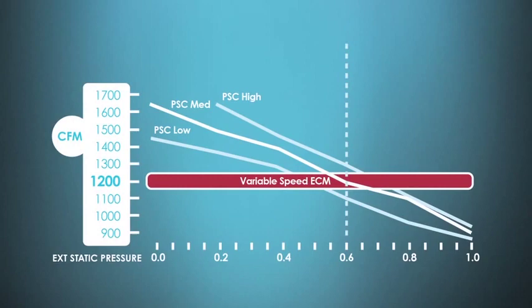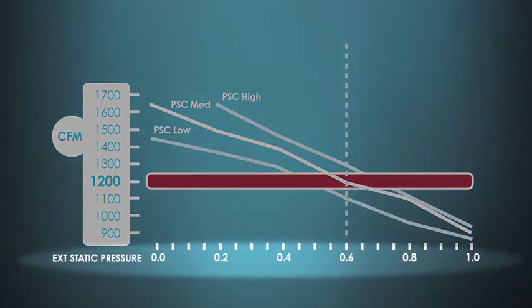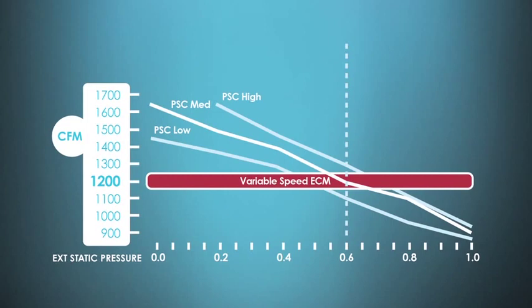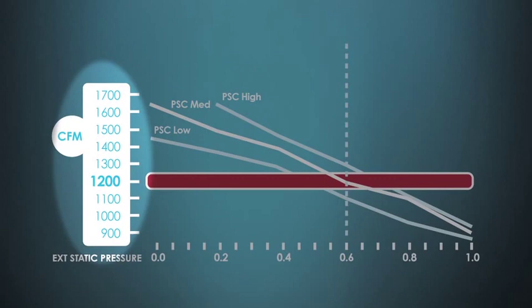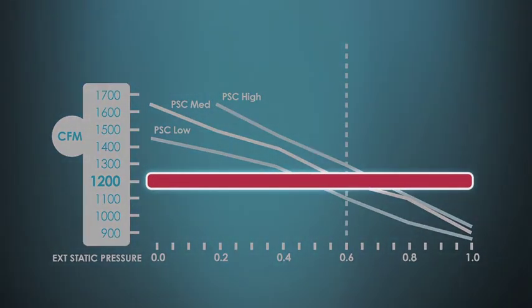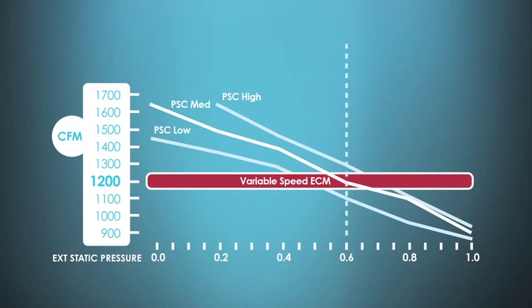Now let's look at how the variable speed motor can maintain airflow and why a PSC motor cannot. On the chart, external static pressure numbers go across the bottom from zero up to one inch total external static pressure. External static pressure is simply a measurement of the resistance to airflow in the duct system — the smaller the duct, the more dirty the filter, the more registers that are closed, the higher your external static pressure. On the left side we see CFM, and we'll go with the industry standard of 400 CFM per ton. The variable speed motor selected for 1200 CFM for three ton of cooling will maintain 1200 CFM all the way up to one inch of external static pressure.